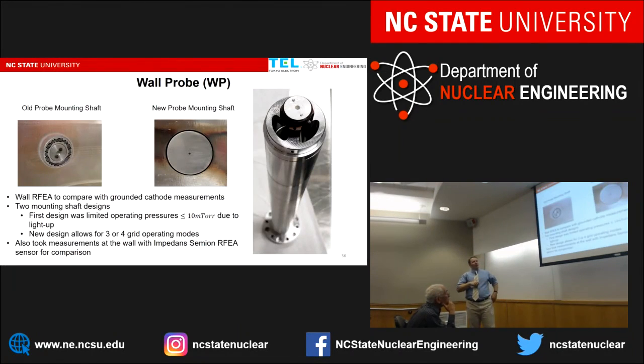So along with the electrode probes, we wanted to also put one in the side of the chamber. So we designed these 2 wall probes, and the purpose for 2 of them you'll see in the next slide. But basically I wanted to give you a picture of what they look like and where they sat. They sat in the sidewall like this, where this is just a cover to prevent any plasma from going past the probe. We wanted the probe to sit right at the wall, so we wanted it to act like a plasma stop. And then in the new one, we changed it so we didn't even need this cover. We just made it the complete size.